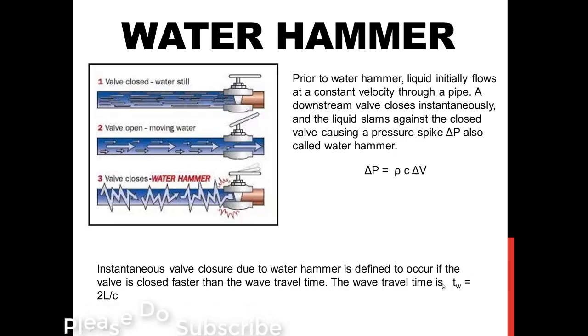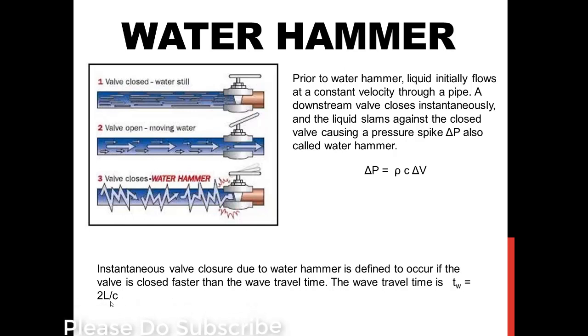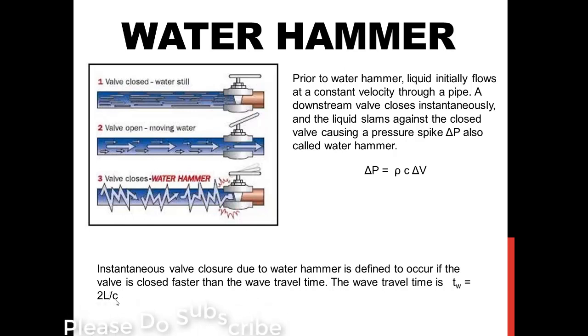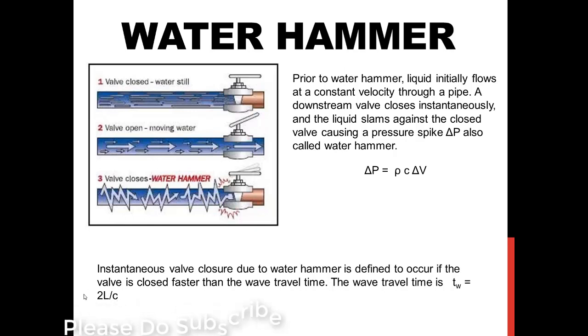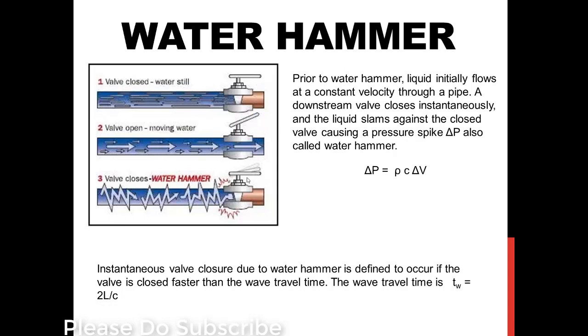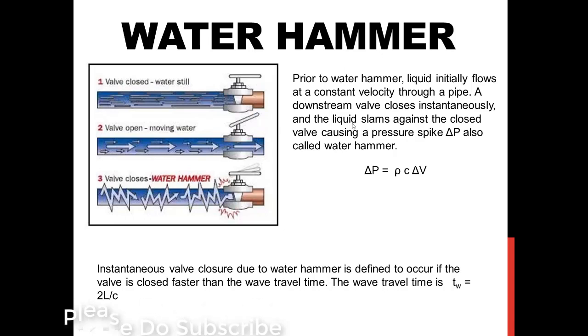At least the time required to close the valve should be 2L by C or less than that. If the length is 100 meters, so 2 times 100 meters by velocity of sound in water, if you take as 1495, that should be the time with which you need to close your valve in order to have this water spike or water hammer or pressure spike.